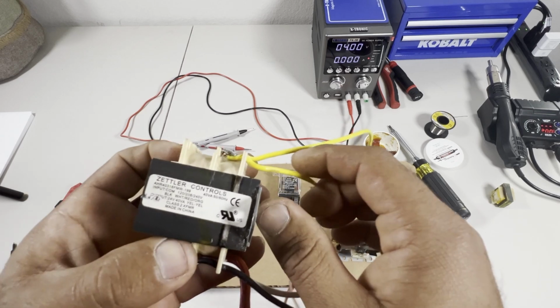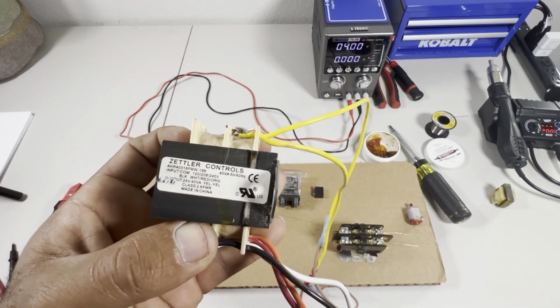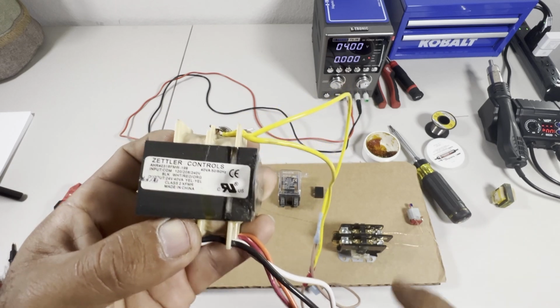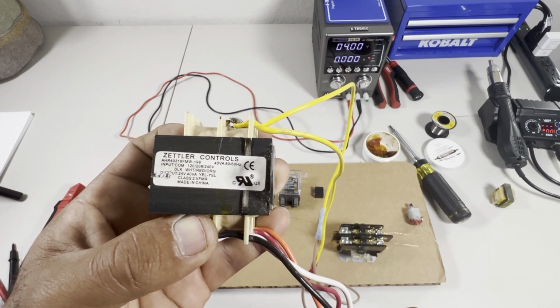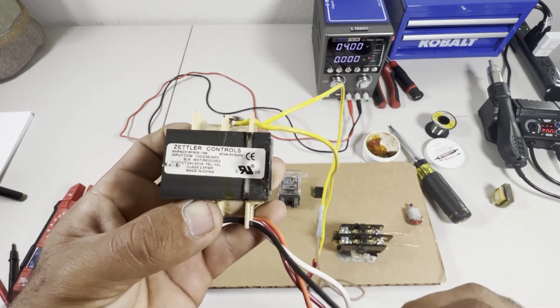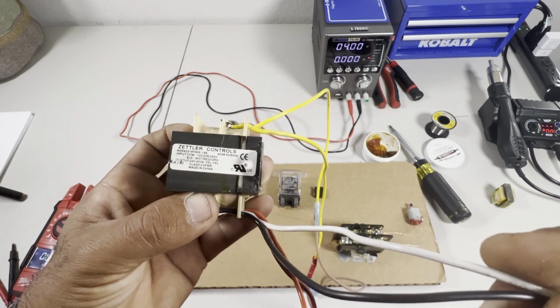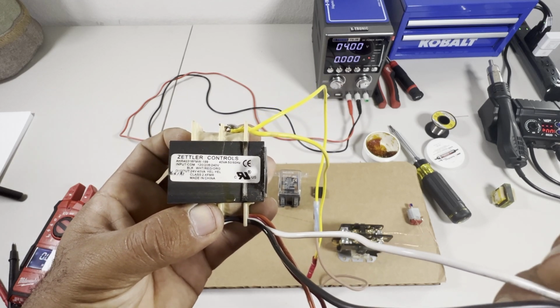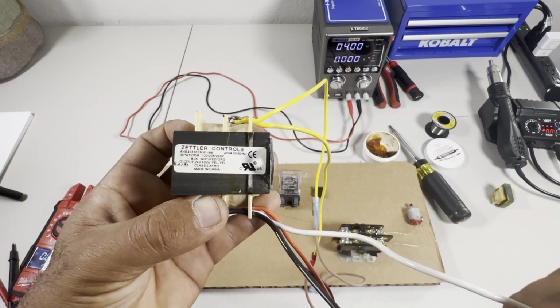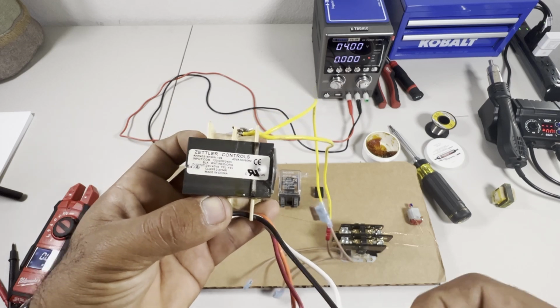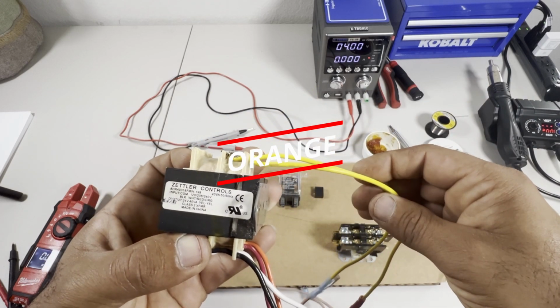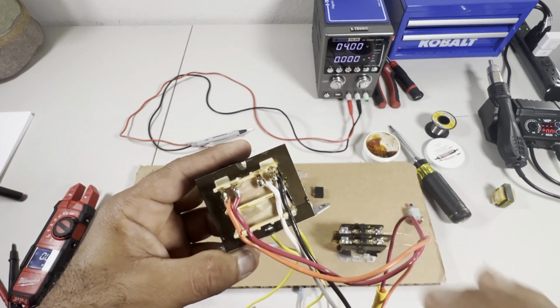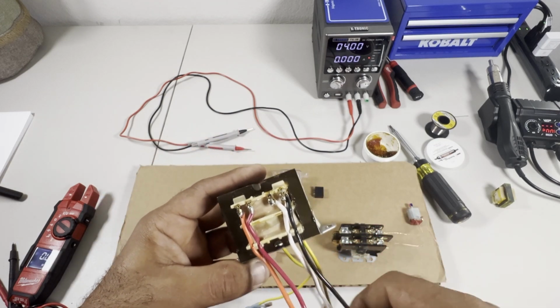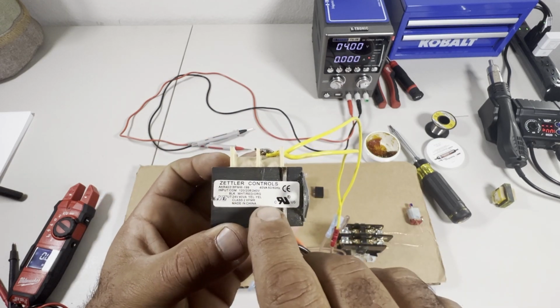And as you can see, this one is a tri-voltage transformer. If you use the black as an input, as a common wire, with the white one, you can get the 120. You can use it in a 120 circuit and you get 24 volts out of it. Now if you use the black with the orange on the 208 circuits, you can get 24 volts out. And if you're using the black one with the red one at 240 power, you are still going to have 24 volts. There is a set of wires and it just goes around, and it has some different tabs coming out of the transformer for that purpose.